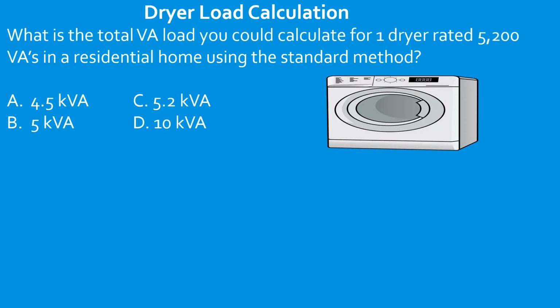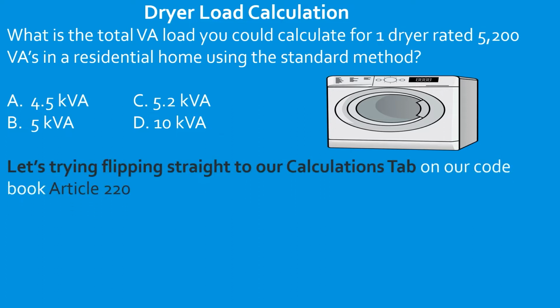What is the total VA load you would calculate for one dryer rated at 5,200 VAs in a residential home using the standard method? So it's basically asking the same thing. We're dealing with the standard method. How many VAs are we going to calculate? I want us to try a new technique here, flipping straight to our calculations tab. The reason is that we're starting to see a theme: every time it has to deal with calculation, we end up back in Article 220. Now that's not going to be universal, but it's going to be very often. So let's try flipping straight to our calculations tab and just using the black bold heading method.